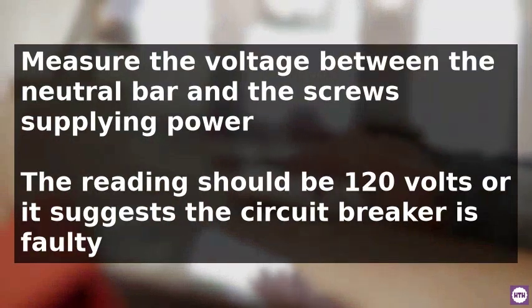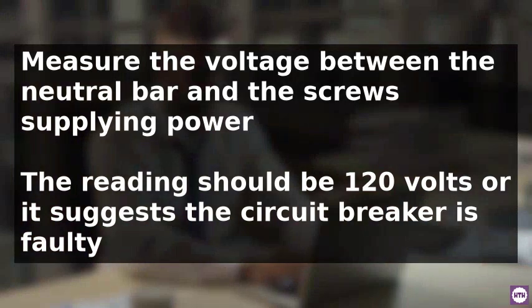Additionally, measure the voltage between the neutral bar and the screws that supply power to the dryer outlet, which should be 120 volts. If the reading is different, it suggests the circuit breaker is faulty, and it is recommended to contact a professional for further assistance.